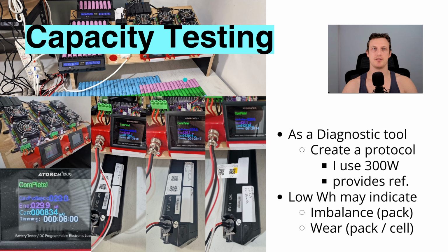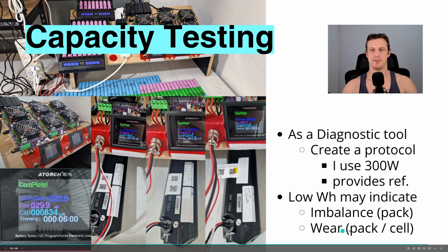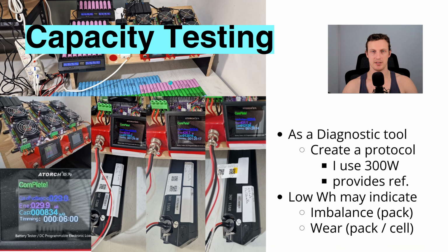And on individual cells, capacity testing is very useful if you are getting into repacking, for the purposes of measuring and ensuring that the cells you use, whether new or second-hand, have enough capacity for the job. To summarize, when capacity testing is used as a diagnostic tool, low watt hours may indicate a pack imbalance, or there is wear or a reduced state of health on the battery pack or individual cells.